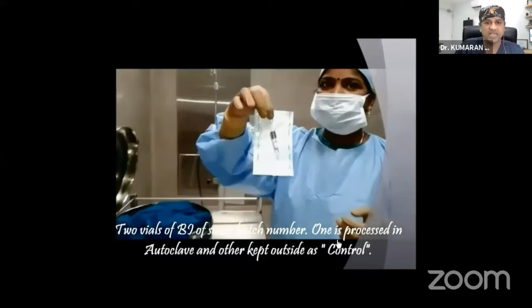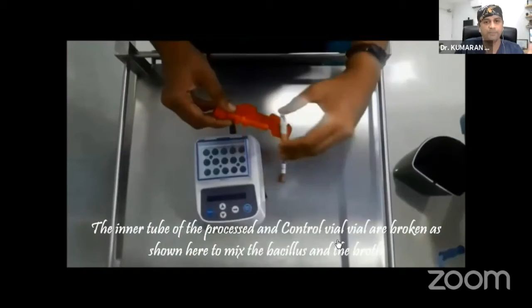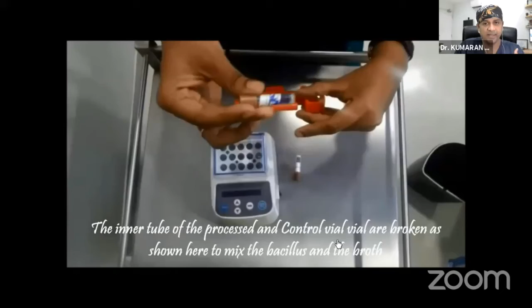The biological indicator has to be placed inside the autoclave the way it is packed. One has to be kept outside and one processed in the autoclave. After the autoclave is done, both the indicators are taken. The inner tube is broken as shown here, and they are incubated in a biological indicator incubator at around 57 degrees Celsius for 48 hours. It is very important to break the inner tube, otherwise you will make the whole process a waste.